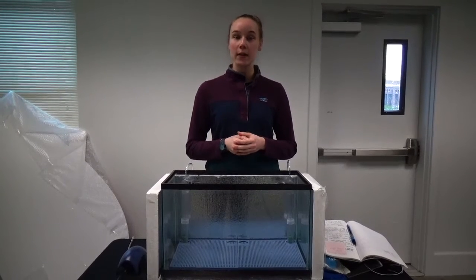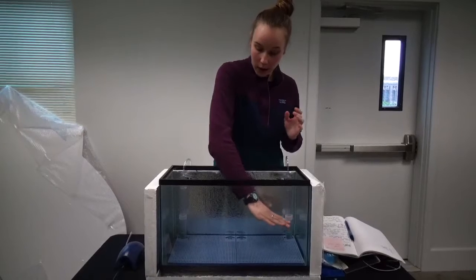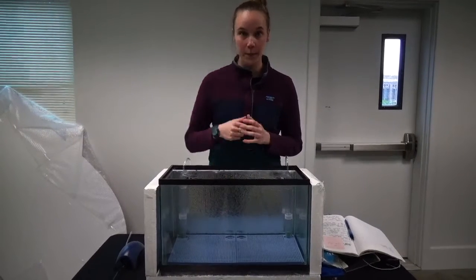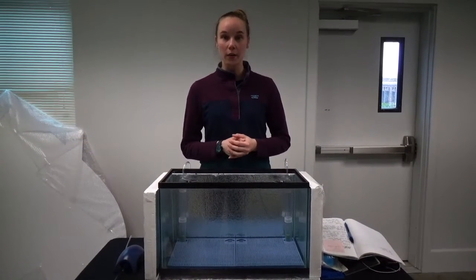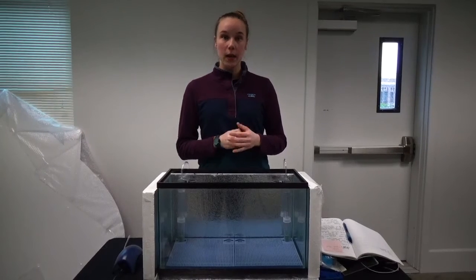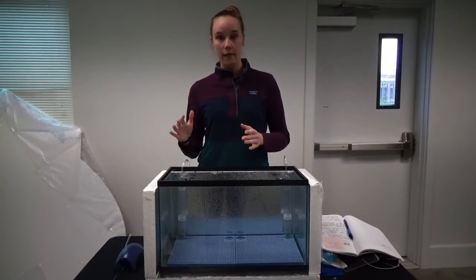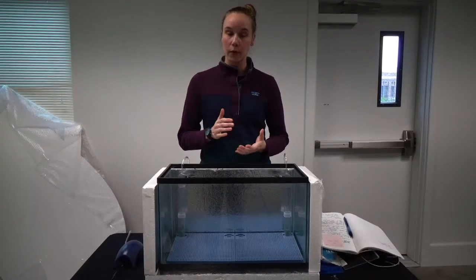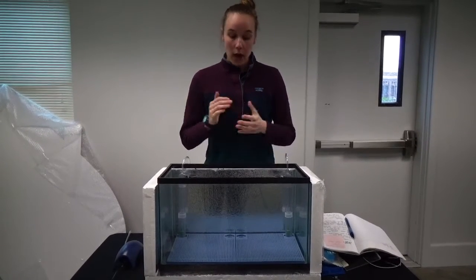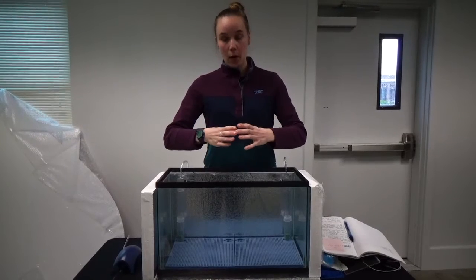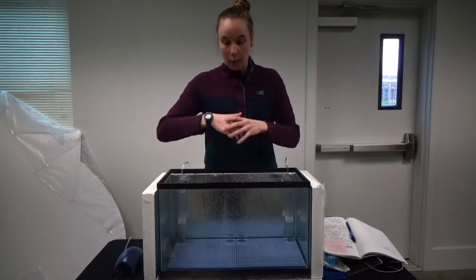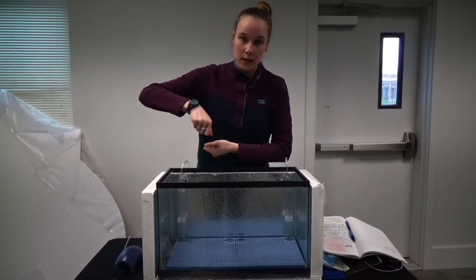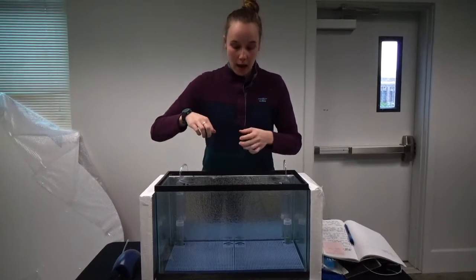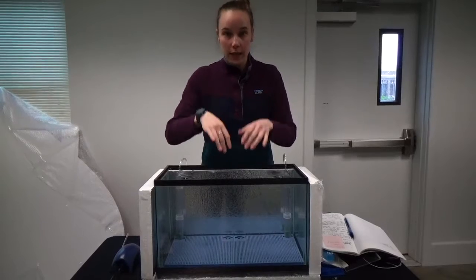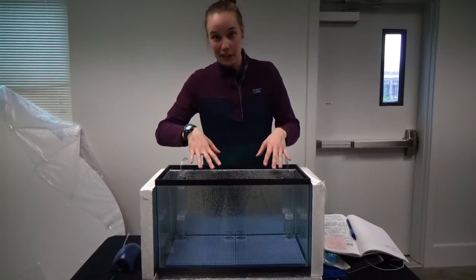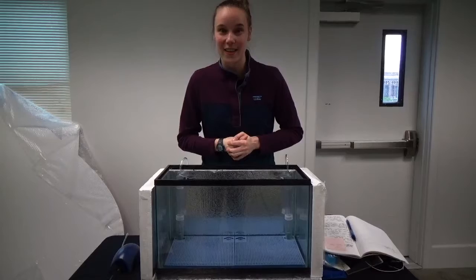You're going to need about 2 pounds of gravel per gallon. Put the gravel down on the plate nice and even. After that, add your bottled spring water. It's going to be about 10 gallons, but you want 11 gallons, a little extra in case of evaporation or water loss. The best way to do this is to have a small plate or cup set on top of the gravel and pour into that, so the water disperses instead of going directly onto the gravel you just evenly spread onto the filter plates.